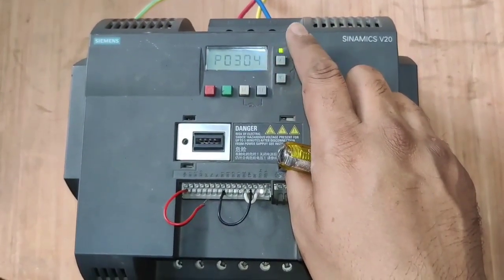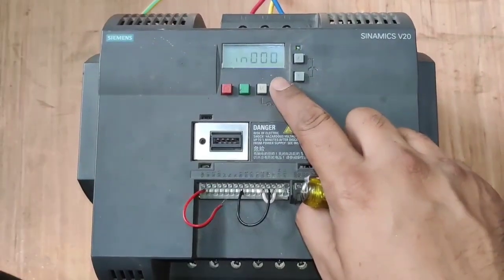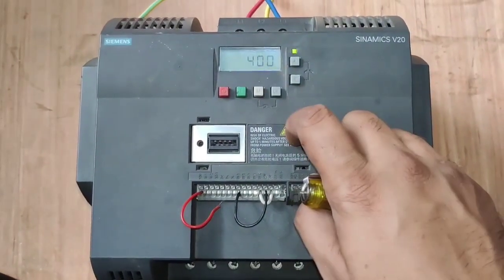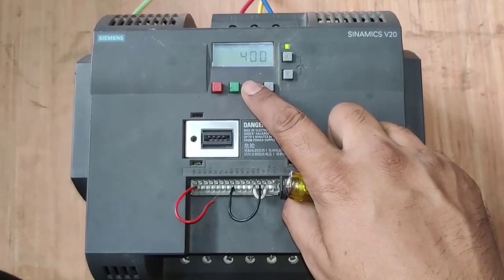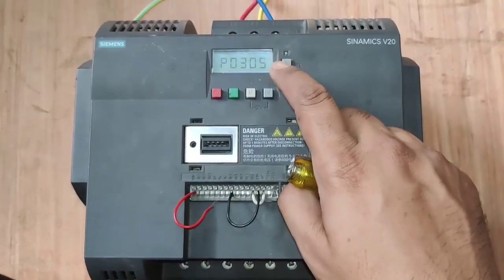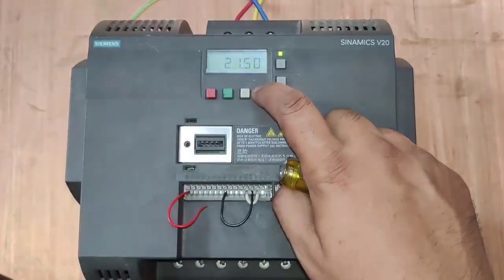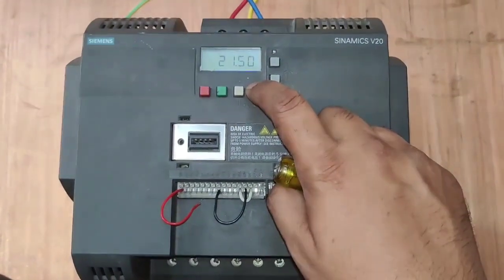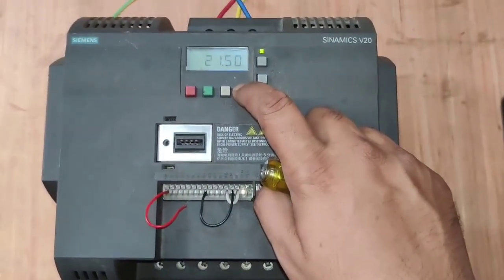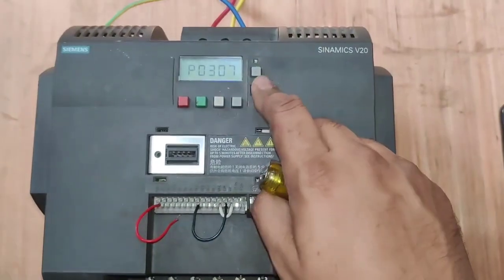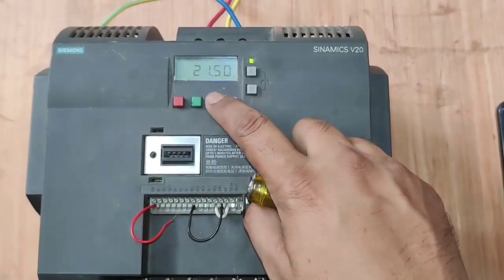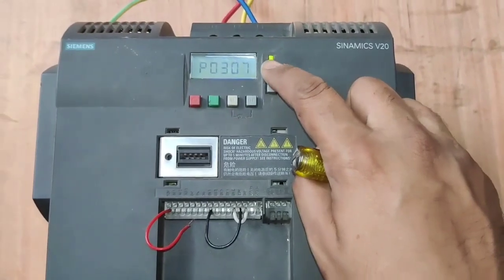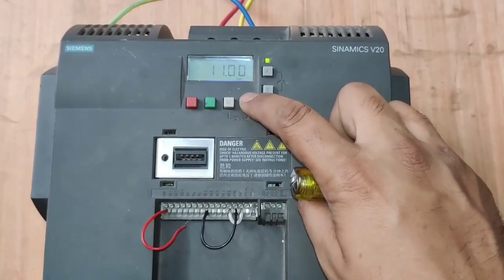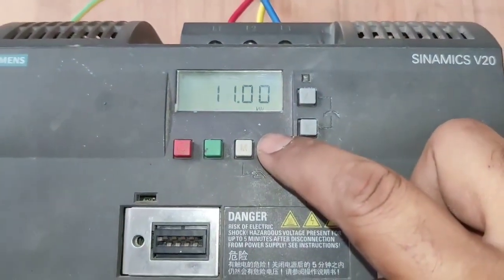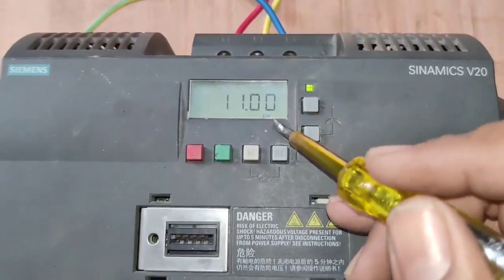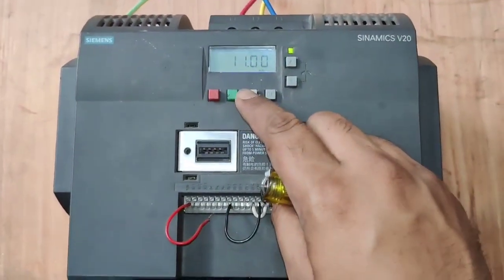Next parameter is P304. P304 is for rated motor voltage, so you can set the rated motor voltage. Next parameter is P305. You can see here rated motor current or overload current you can set in the P305 parameter. Next parameter is P307, by increasing with the up key. P307 is for rated motor power. You can see here in P307 we enter the rated motor power in kilowatts.